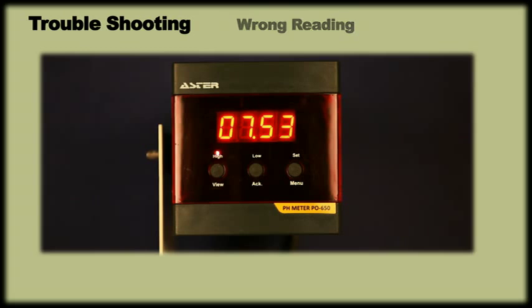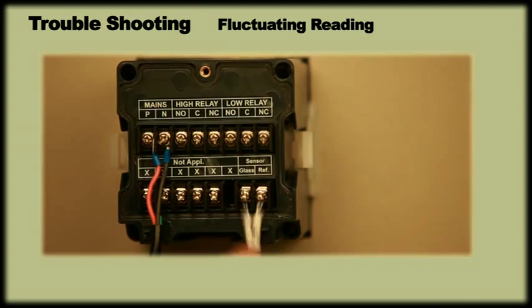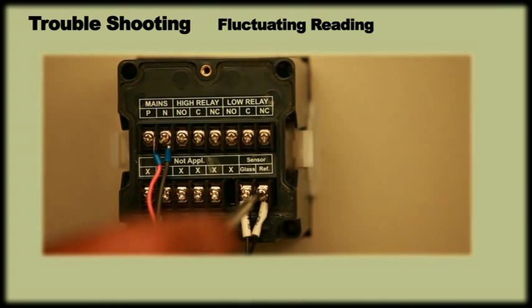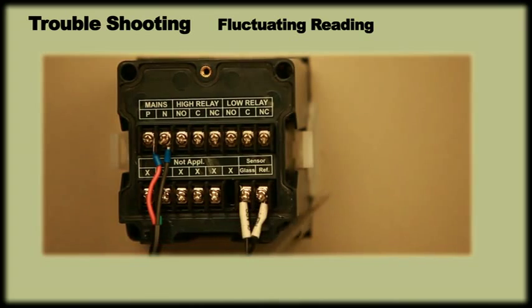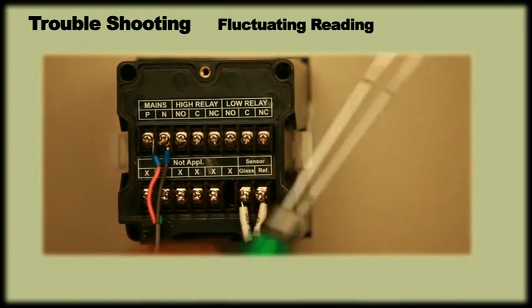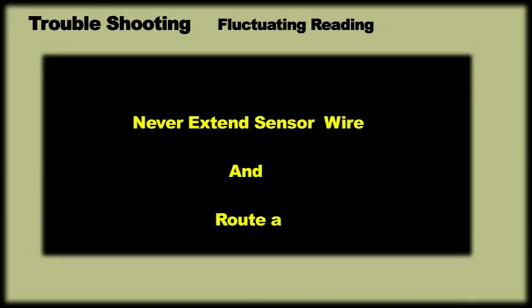Contact Service Center if meter reading is fluctuating. Ensure that the sensor cable is directly terminated on indicator terminal without any extension joints in the cable. See if there is any loose wiring. If sensor wire is routed along with power cable, then isolate the sensor wire.